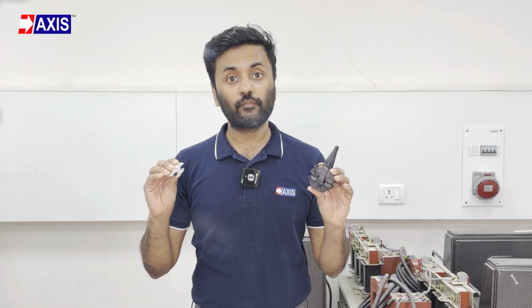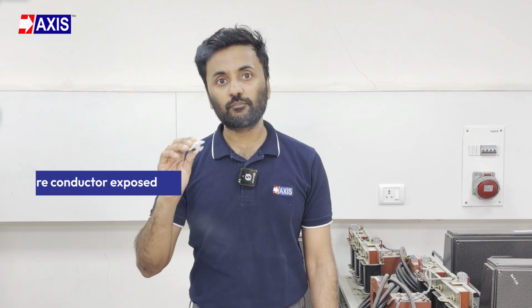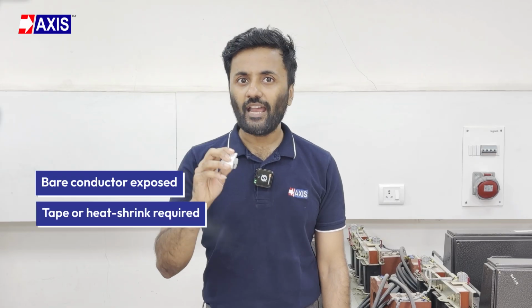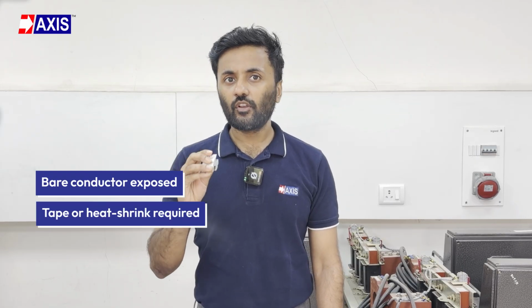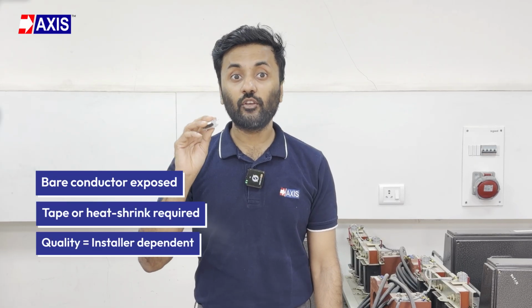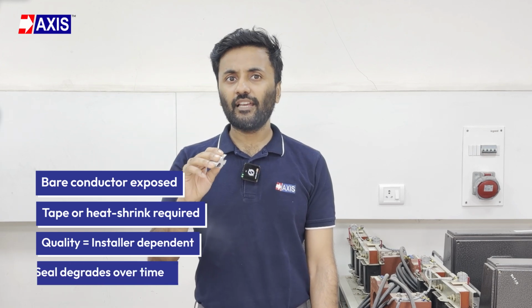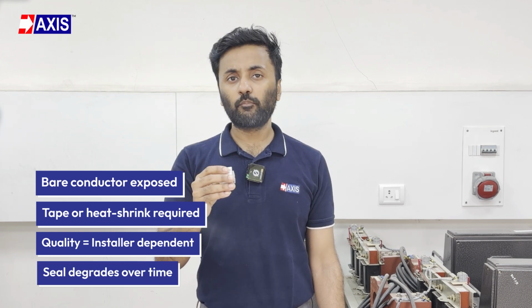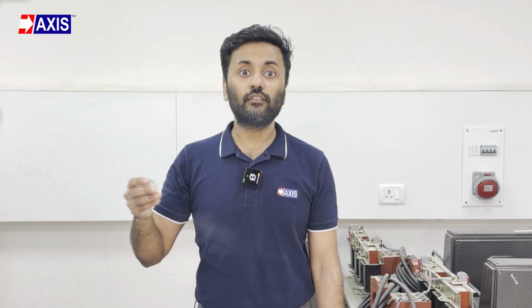Now, here's the critical difference between these two: the environmental factor. With an H connector, you strip the cable to make the connection, and this exposes bare conductors. After crimping, you must seal and insulate the connection by wrapping tape or adding a heat shrink sleeve. The quality of the connection depends entirely on the installer. Over time, that sealing can degrade: UV exposure will break down the tape, temperature cycles will crack the seal, and moisture will eventually seep in.